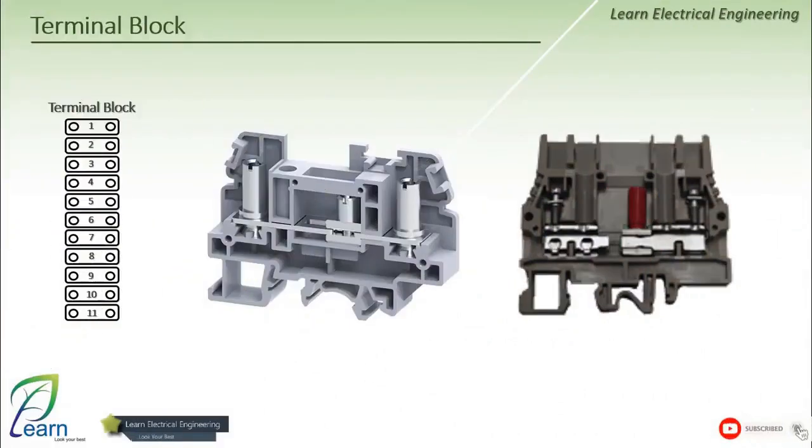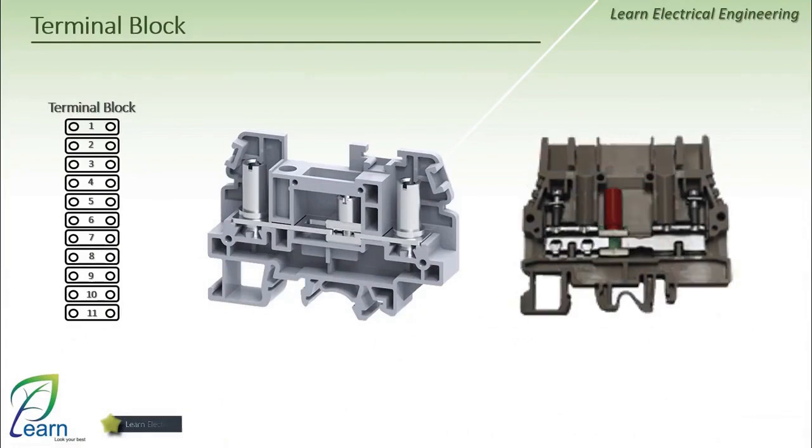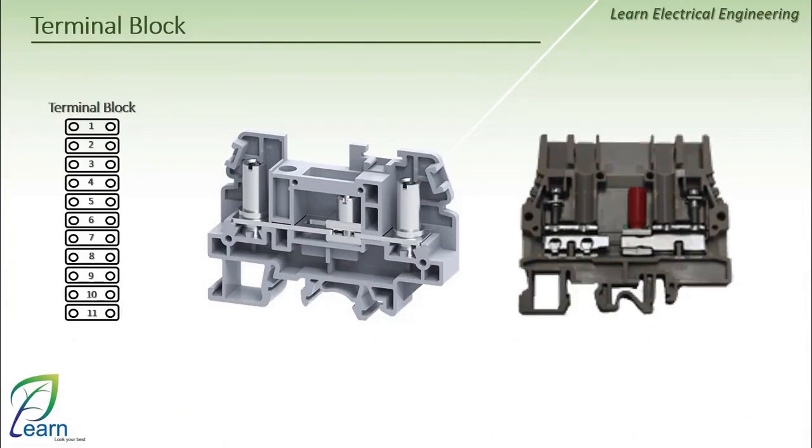The second thing is the terminal block, also known as the rosetta. The terminal block is used for many reasons, including the ease of connecting wires to it, as opposed to connecting them directly to the equipment, where you might not be able to connect more than one wire at the same point. However, if we use the terminal block, we can use more than one terminal for the same purpose, considering that you have jumpers between them and you exit with just one wire.